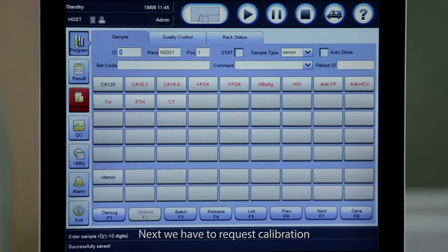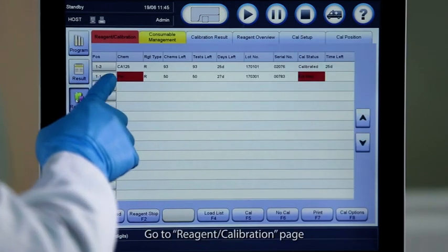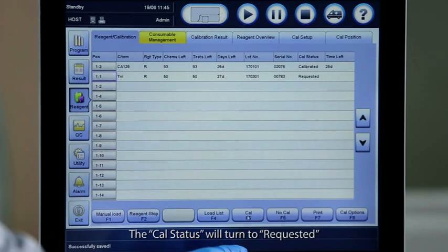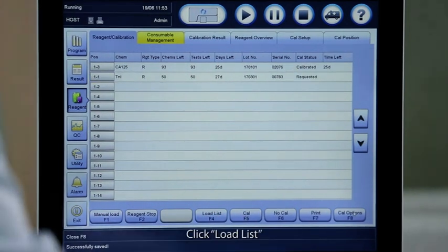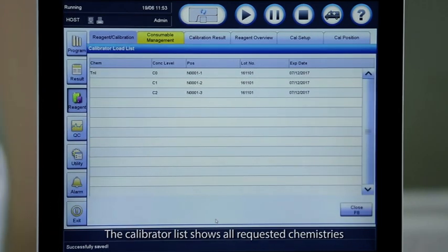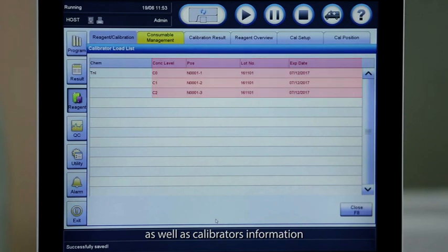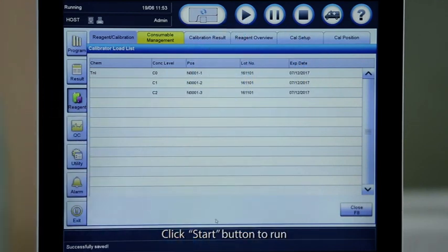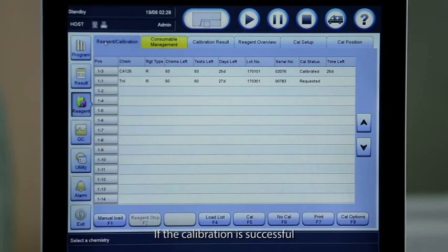Next we have to request calibration. Go to Reagent Calibration page. Select the chemistry that needs calibration. Select Cal. The cal status will turn to Requested. Click Load List. The calibrator list shows all requested chemistries as well as calibrators information. Load calibrators according to the calibrator list. Click Start button to run. If the calibration is successful, the status will change to Calibrated.